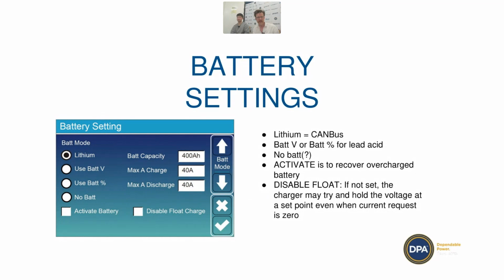And then we've got battery settings. So if you're doing managed batteries, you're going to set it to lithium, and you're going to set it to activate battery, and you want to disable the float charge. Battery capacity, you're going to set according to the amp hour capacity of your batteries. So say you're using Discover rack mounts, you've got 4 of them, you're going to put 400 amp hours. But because it's managed, it doesn't actually really matter, because the battery is calculating the state of charge instead of the inverter. And then you've got max charge and max discharge.